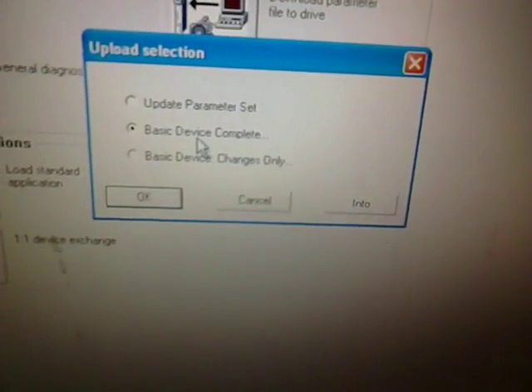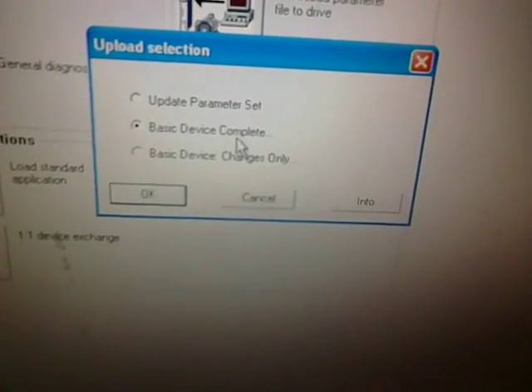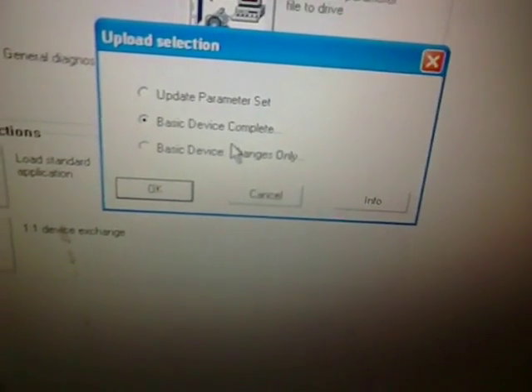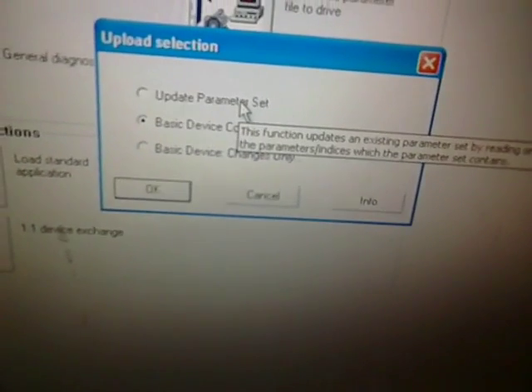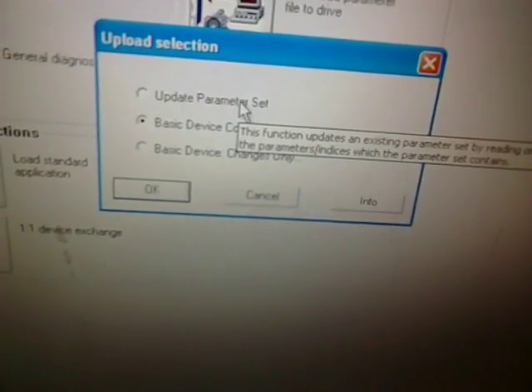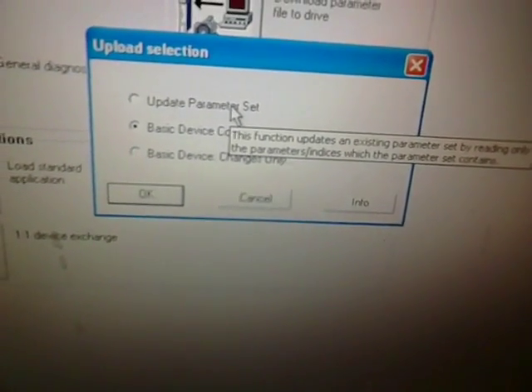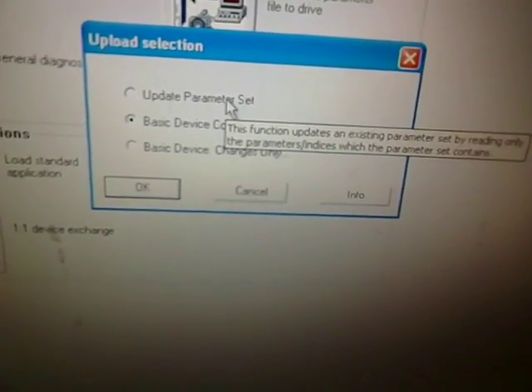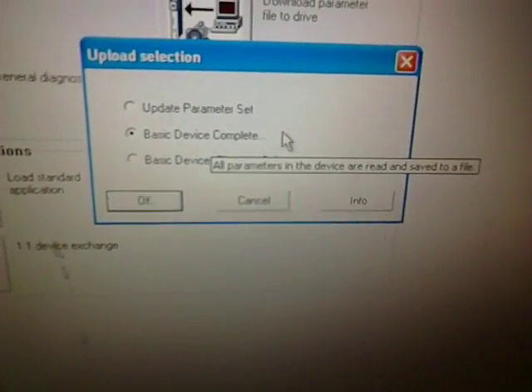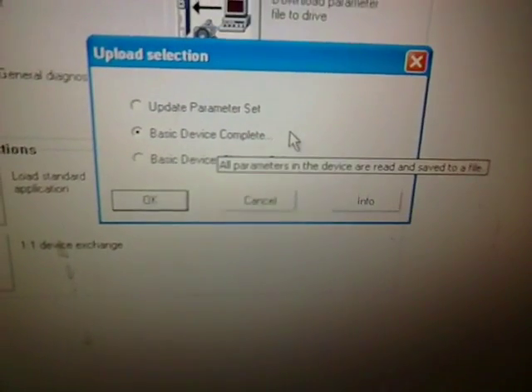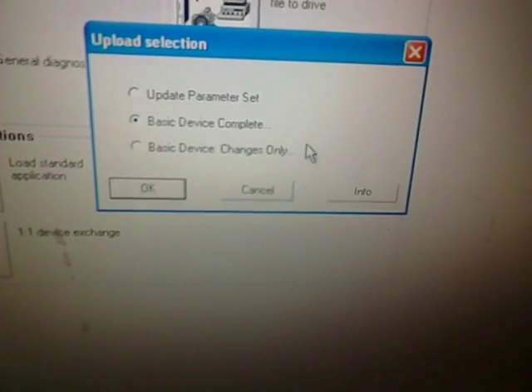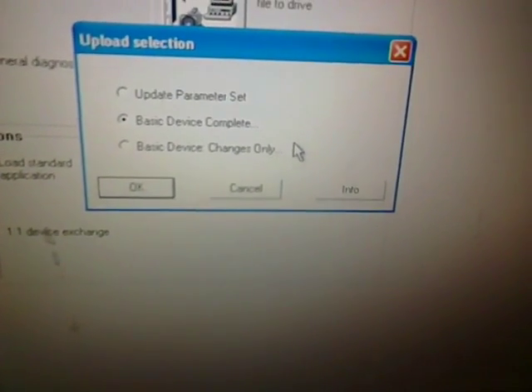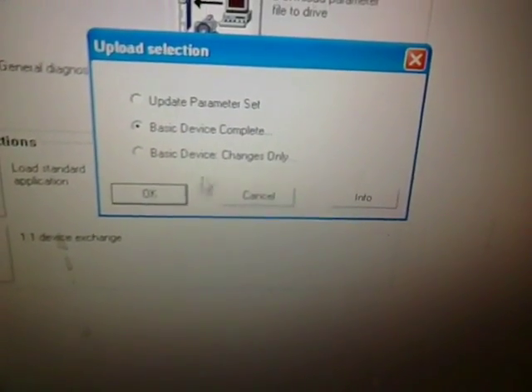It will give us three options. The first one is update parameter set, the second is basic device complete, and third one is basic device changes only. If we have an older file and parameter is changed in this mode, I mean in the software, and we want to update that file, we will select this option. The second option is to install the complete parameters that are present in our drive after reading from the drive. And the third one is only if we want to save only the changed parameters that we changed by this software. We will choose the second option.